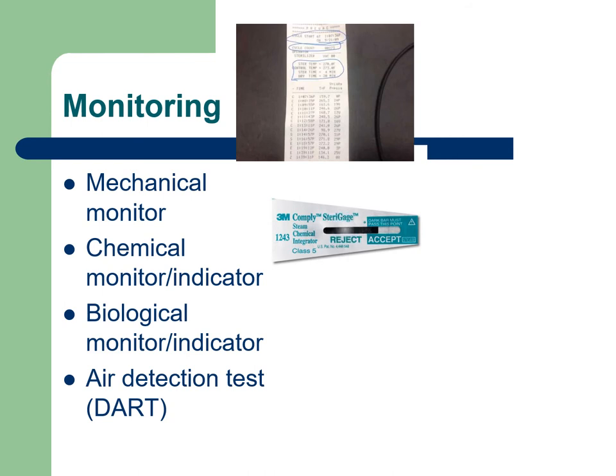Something else we've already talked about, and you're seeing these in the lab, are the chemical indicators, or integrators as they are called. There are a variety of flavors of chemical indicators, there is not a one size fits all. You can see this one specifically says steam chemical integrator class 5. It also tells you that the dark bar must pass this point, and the dark bar is in that acceptable area. So this is something we always check with every single item that's steam sterilized, it should have one of these integrators. There are class 1, 2, 3, 4, 5, and 6 integrators, with class 5 being the most common because it reacts to all the critical values over a specified range in the sterilization process, which makes it more accurate. So these are used most commonly.